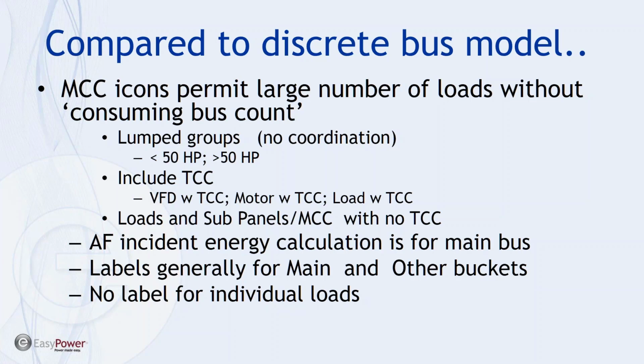One disadvantage of using the icons is the arc flash incident energy is calculated for the main bus. Now normally this is going to be a 480 volt system. If we're talking about a 240 volt motor control center, it's not necessarily a disadvantage because that's where the scope of most projects will remain or extend to.